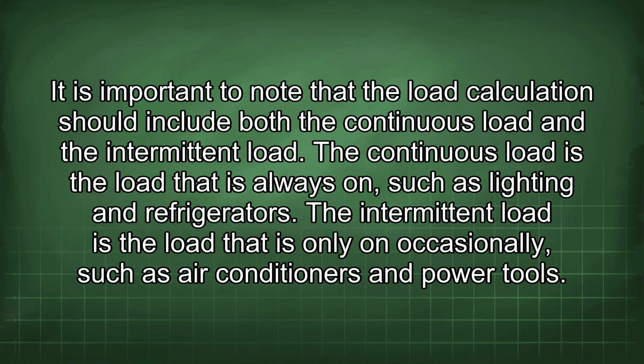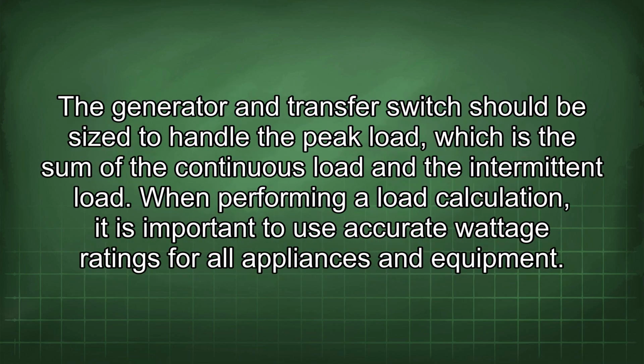It is important to note that the load calculation should include both the continuous load and the intermittent load. The continuous load is the load that is always on, such as lighting and refrigerator. The intermittent load is the load that is only on occasionally, such as air conditioners and power tools. The generator and transfer switch should be sized to handle the peak load, which is the sum of the continuous load and the intermittent load.